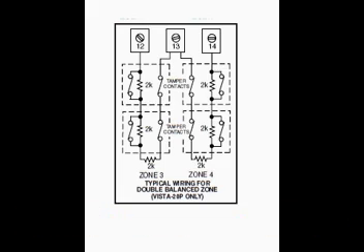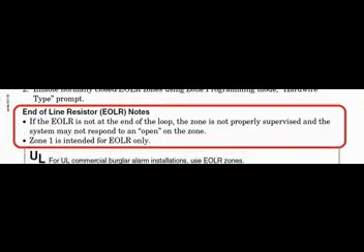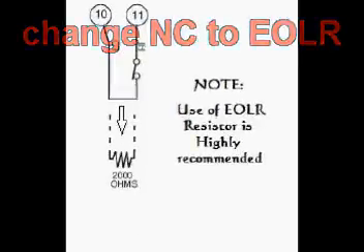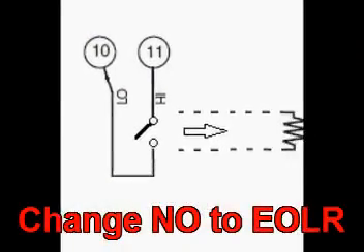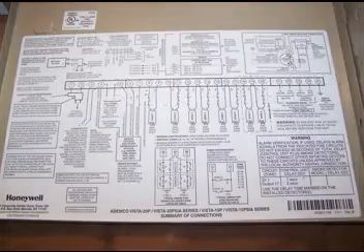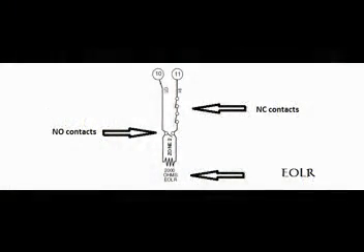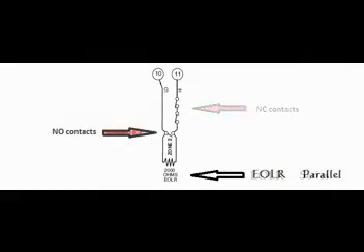Finally, we have type 4 — the double balanced zone. As far as I can tell, you'd only use this if you were setting up a system for high security, as every sensor has tamper protection built into it. You'll find zone type descriptions on page 2-6. One very important note on that page: if you don't use an end-of-line resistor, they can't guarantee your alarm panel is going to work correctly. So if you've already hardwired your system normally closed and want to add an end-of-line resistor, simply add it in series. To add an end-of-line resistor to a normally open circuit, add the resistor in parallel.